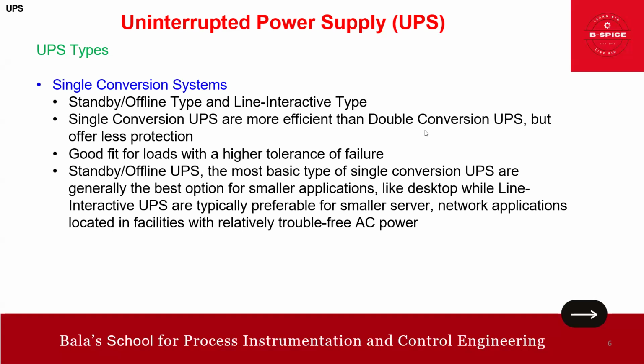Otherwise, we have to go for double conversion. So standby offline UPS, the most basic type of single conversion UPS, are generally the best option for smaller applications like desktops, while a line interactive UPS is typically preferable for a smaller server or network application located in a facility with relatively trouble-free AC power.